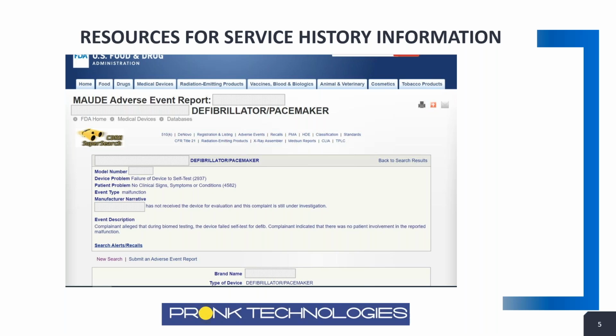You can see here, they would show you the model number of the device, and what the problem in the field with that device was: the self-test did not pass, it malfunctioned. And they're waiting for the manufacturer to receive the device to investigate it. So it gives you a status of what that medical device incident is going through. And down below, it gives you an event description. It shows you that during biomed testing, the device failed to self-test.